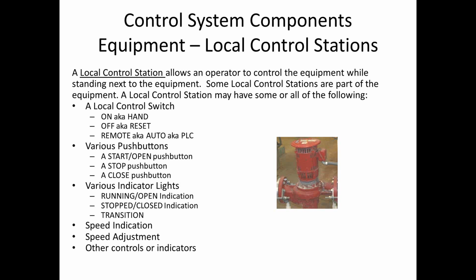You could put that into the off if you were going to take a piece of equipment offline and didn't want it automatically started. Some PLC programmers actually use that switch to reset and acknowledge any alarms that happen in the plant, so that it forces the operator to go out to the piece of equipment, troubleshoot what's going on, and then they acknowledge the alarm by toggling the local control switch from auto to off and then back to auto. There's also various push buttons that might be on a local control station, a start push button or an open close push button, indicator lights that tell you as you're walking by the piece of equipment if the pump is running or not, or if the valve is opened or closed.